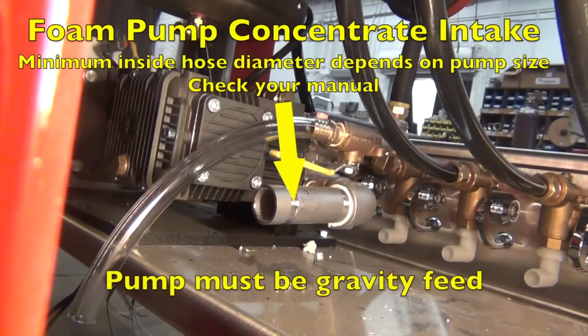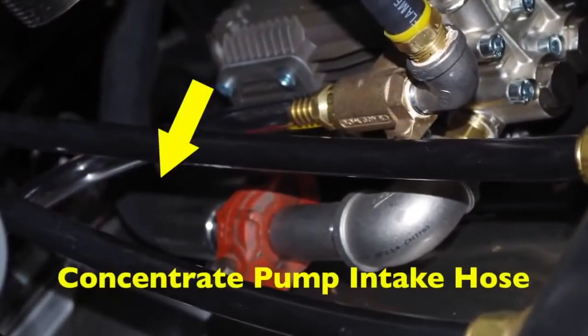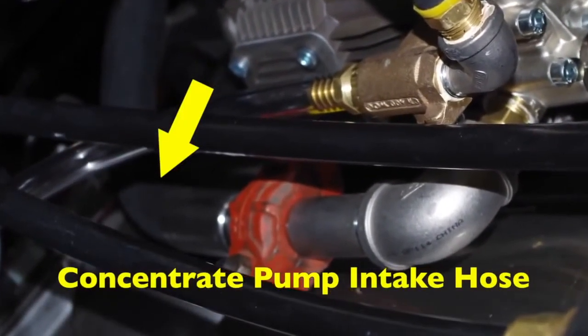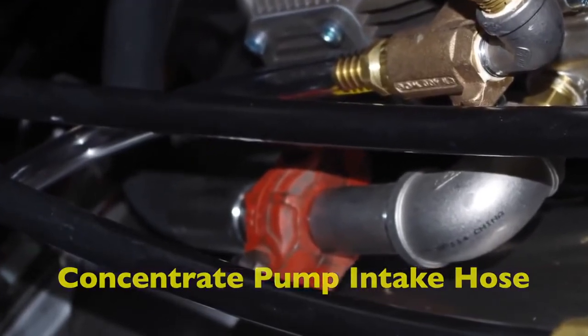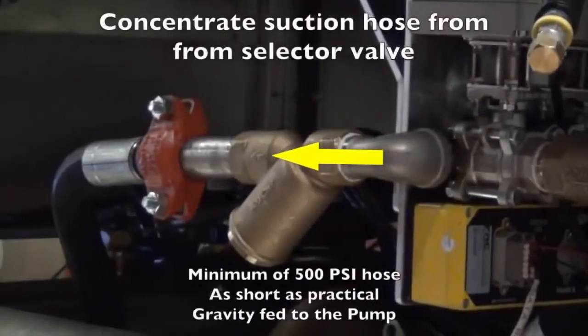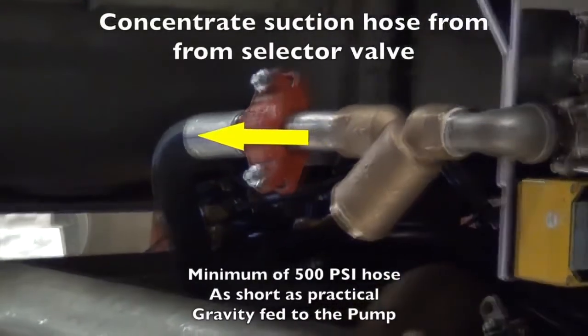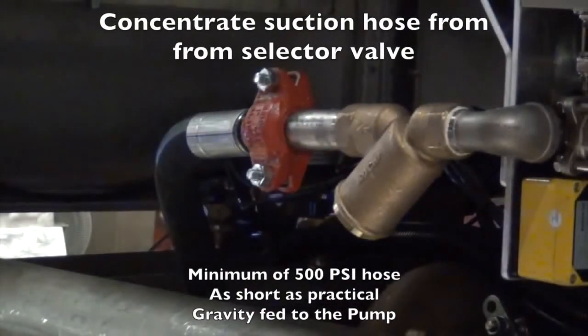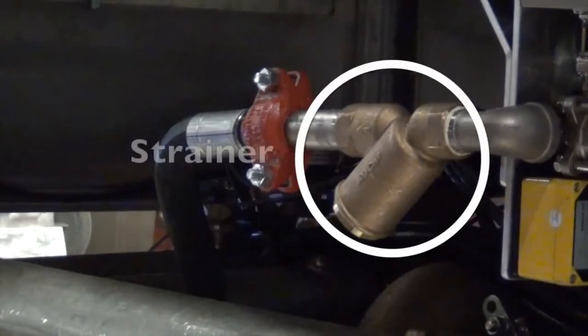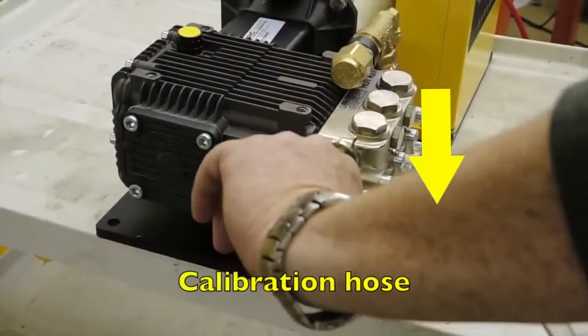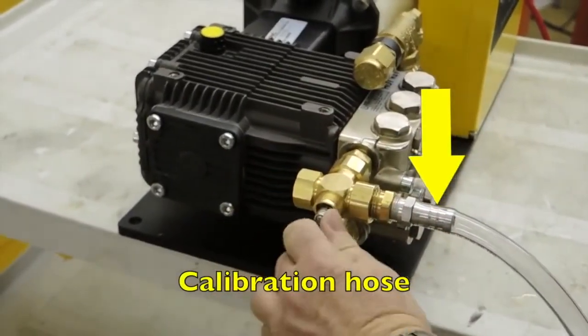This is the foam pump concentrate intake. It must be gravity fed. The hose diameter depends on the pump size. Please consult the installation manual for your minimum hose diameter requirements. All hose lengths on the suction side of the foam pump should be kept as short as practical. All the plumbing between the foam pump and the foam tank check valve must be rated for a minimum of 500 psi. Install a strainer before the concentrate pump. The calibration hose should be accessible for calibration.